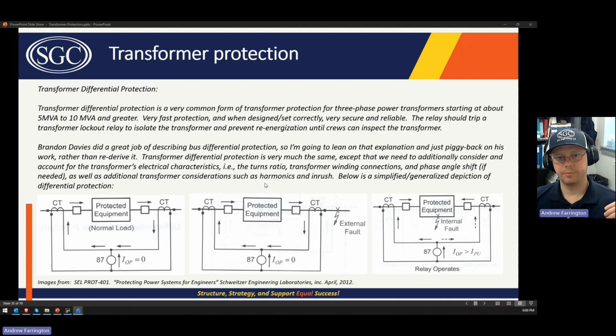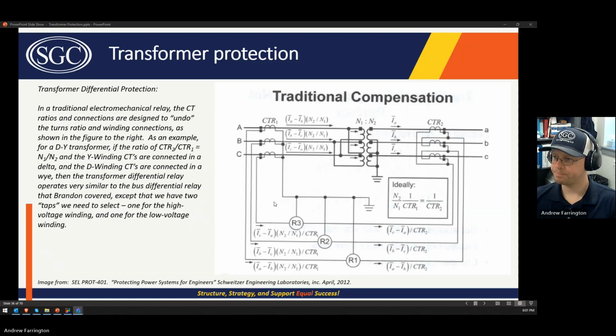We also need to consider inrush and harmonics when we're protecting transformers. Also, things you don't have to worry about when you're protecting a bus. So what we want to start with is a traditional electromechanical differential protection, because the theory is very helpful in understanding how you apply that in a more modern relay. And the microprocessor-based relays are really just replicating what was done historically with electromechanical relays. So if you understand how to set an electromechanical relay, you should be able to understand how to set a digital relay. And we'll go through an example of both, but the theory is important.